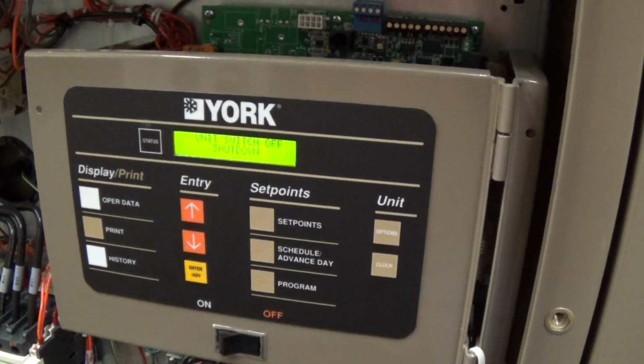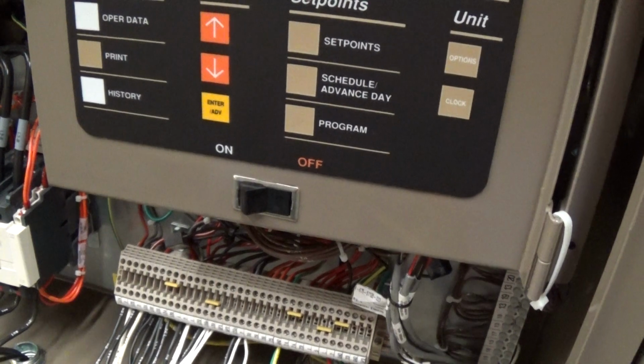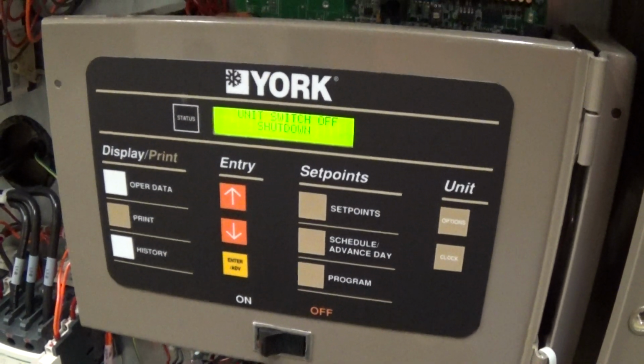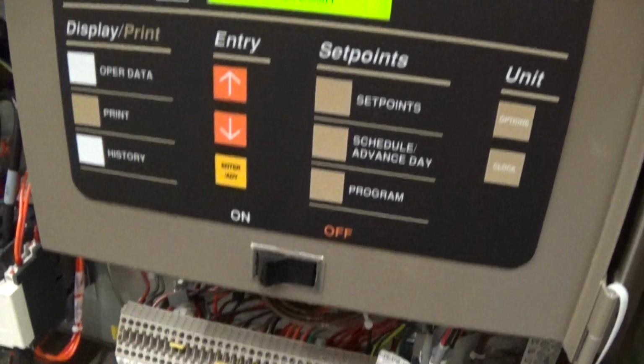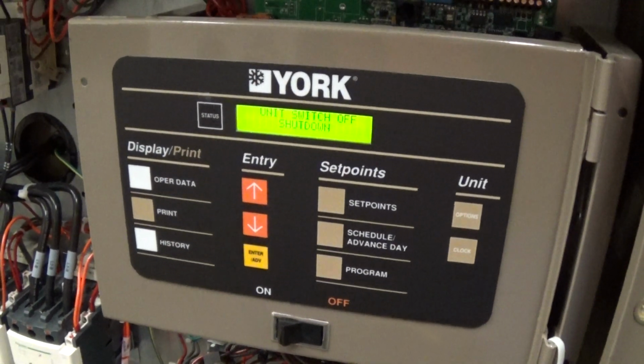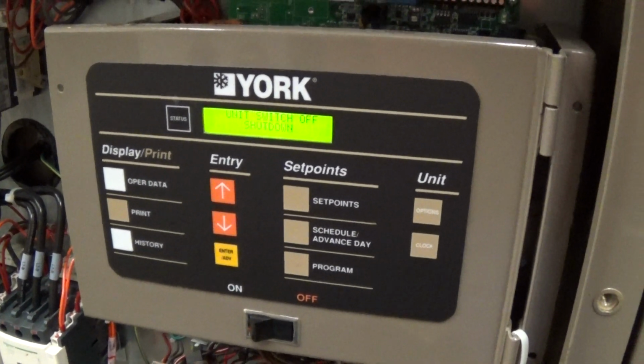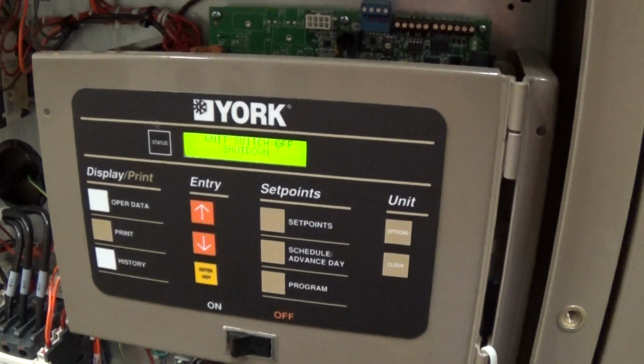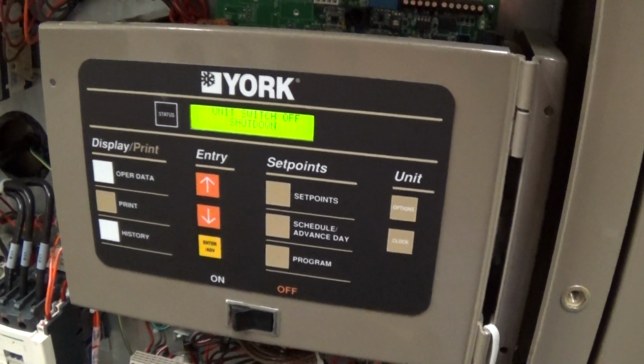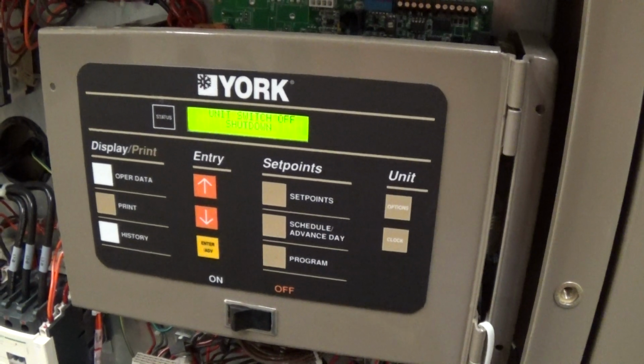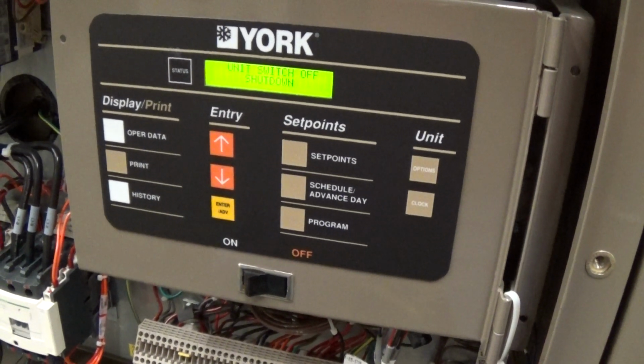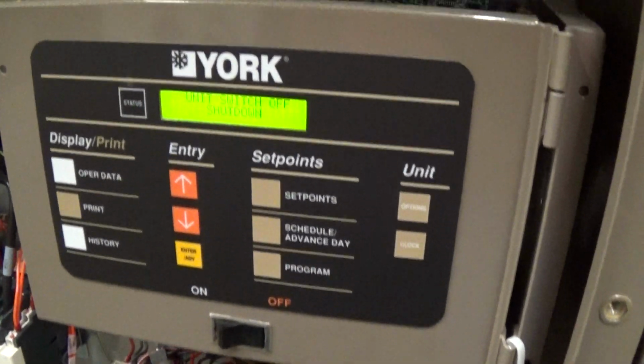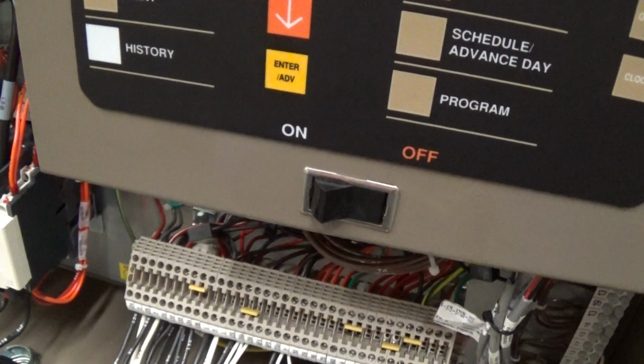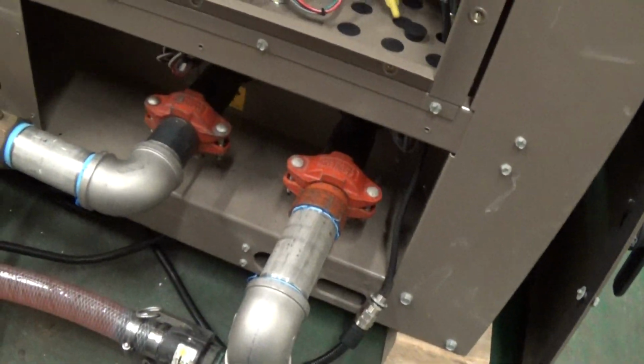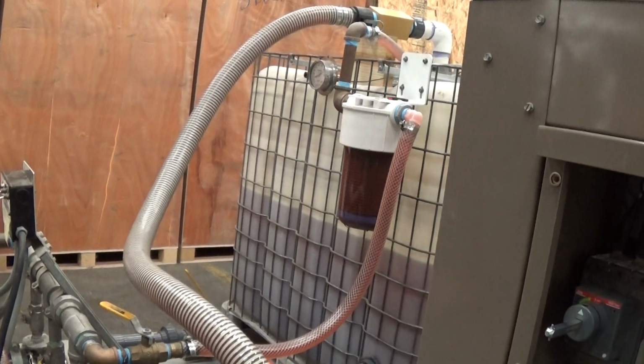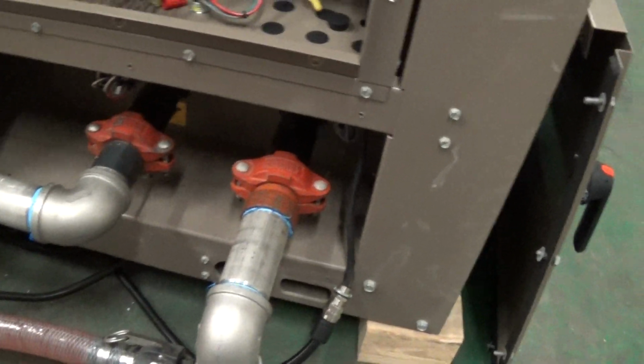When you turn your chiller off, always do it here at the rocker switch, because in this state, as long as you see power on the controller, with this button off, the compressor heater bands are still on, and that's important. If you want to turn the chiller off by the disconnect on your wall, your main power supply, just remember that's only suitable or practical for long periods of time, because if you do a long power down, you want to have the compressor heaters on for at least 6 hours before you turn that switch off. For our demo here, we're using our own pump tank test system, which we've done literally hundreds of times.